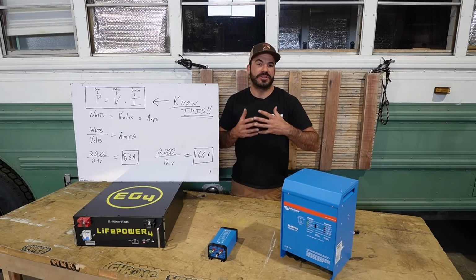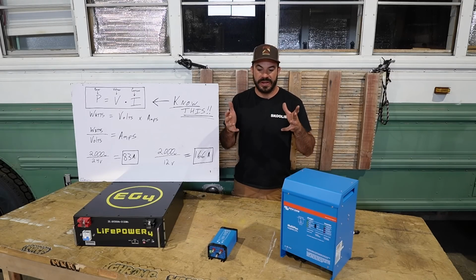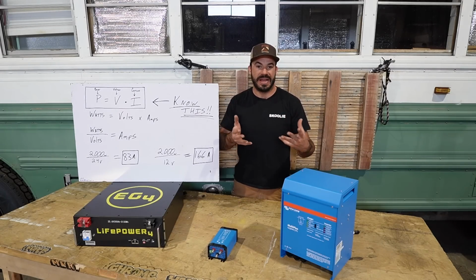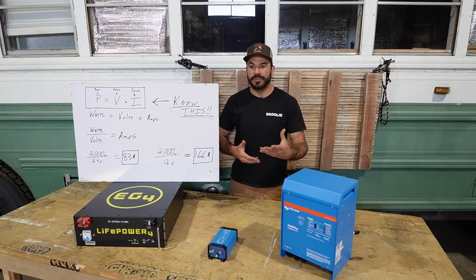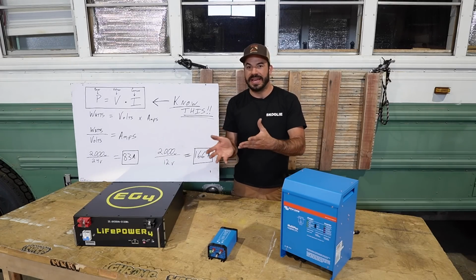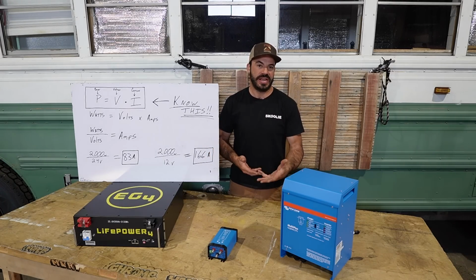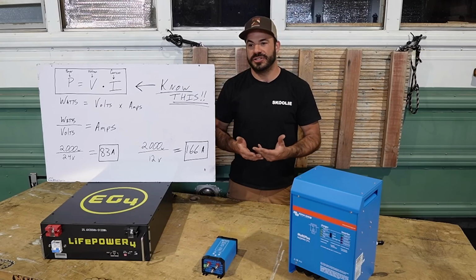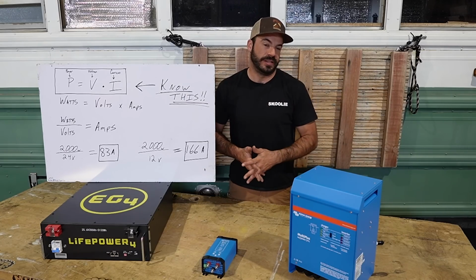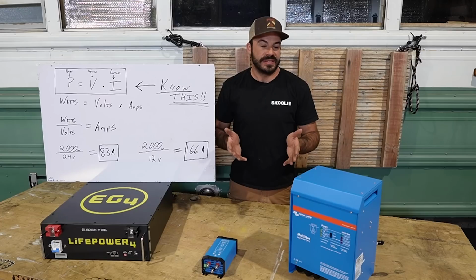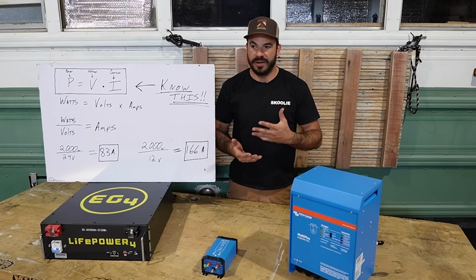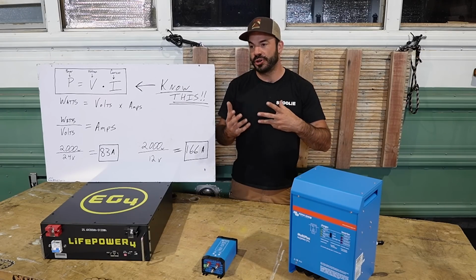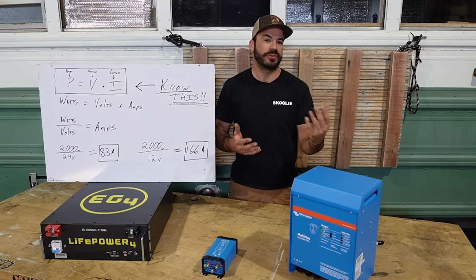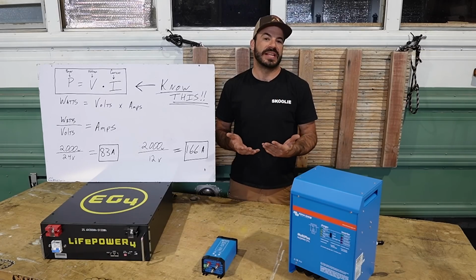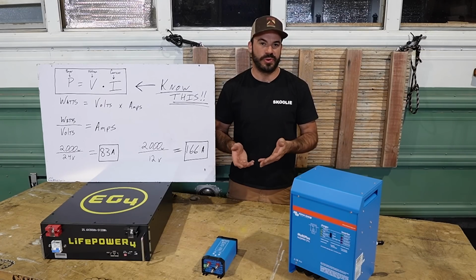As you can see, by changing the operating voltage of an appliance that uses the same amount of power, the amount of amperage required to supply that power changes. What we want to pay attention to when building our off-grid electrical systems is often the amperage rating of the appliances, charge controllers, or solar panels, because amperage is how we decide what gauge of wire to use.